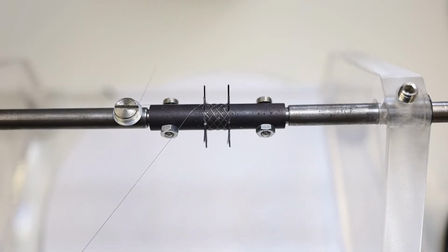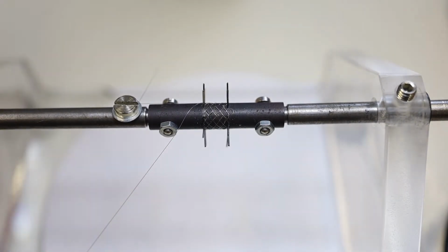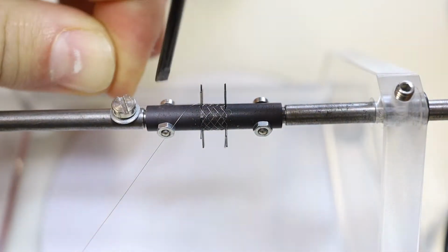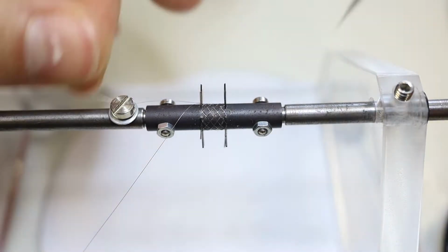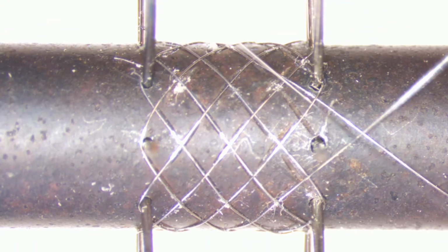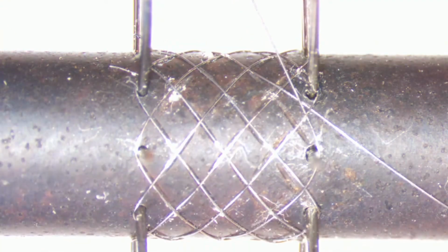When the implant is finished braiding, the 2 ends of the wire must be connected. To do this, detach the wire from the screw. Then, braid the wire back 1 crossing. This fixes the marker band better in the implant. The marker bands are very tiny platinum sleeves. Take them out of the box very carefully and make sure to choose the right size for your wire.